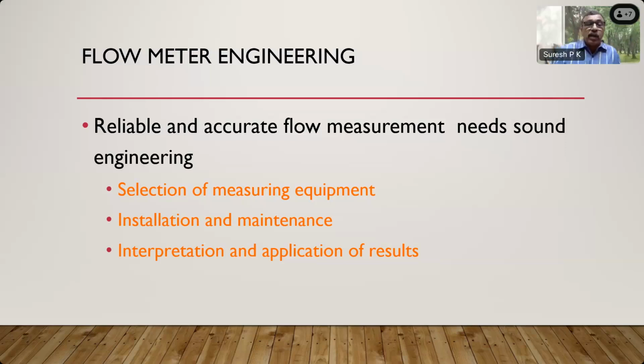upstream length is not there. So that is important. Installation and maintenance of the flow meter is important. In modern flow meters, maintenance checks are available, so you can check the flow meter through its software, or maybe a technician can tell you from the sound itself that the flow meter is not working properly at a particular flow. Because these planned equipments and flow meters have a signature curve. When it is properly measuring, the sound itself gets registered in your head, and the slightest difference in the sound will tell you that there is some problem with the flow meter or the flow.